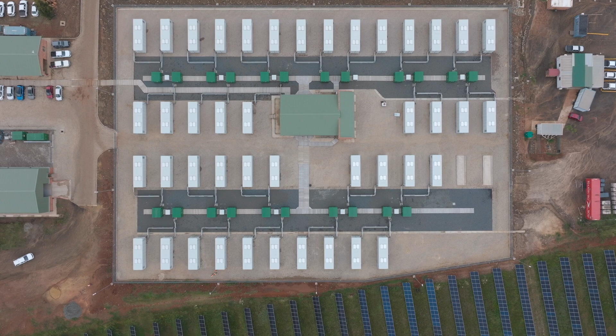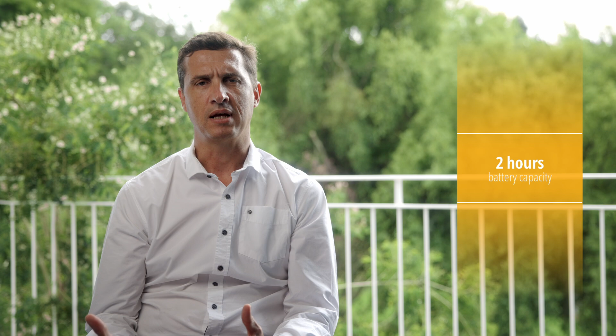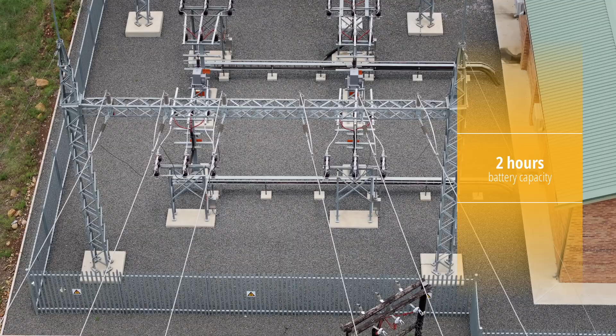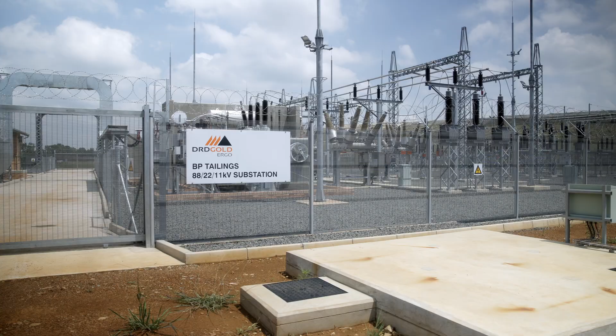The reason we ended up at these size batteries is that in order to shut down the plant in a controlled manner, we need at least 2 hours of battery capacity. Ergo at that stage had 2 feeds: one into the Brakpan tailings dam and one into the Ergo plant. The demand of the Ergo plant is around 14 megawatts and at Brakpan tailings 7 megawatts.